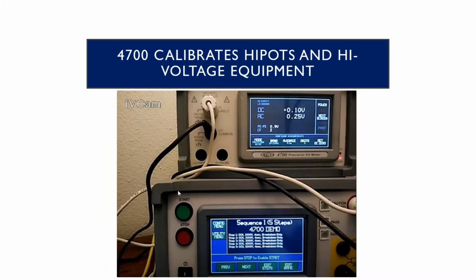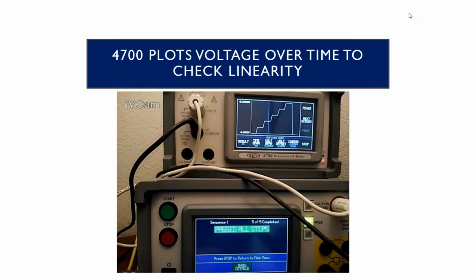So this is a screenshot. Basically, remember we said that the meter is typically used for calibrating hipots. There's a hipot on the bottom, and the meter's on top. And notice it's a dual use meter. It's reading both DC and AC simultaneously. So you can see the DC component and the ripple on top of that. That's one application for that. Notice that we also display the peak-to-peak voltage value and the crest factor. So again, we're very good with high crest factor signals. The system also has the ability to plot the voltage over time. So if you have something drifting with temperature or time, then here's an example of it. In this case, the hipot put out a stair-step signal, and we're looking to see how accurate it is at each of the different levels.